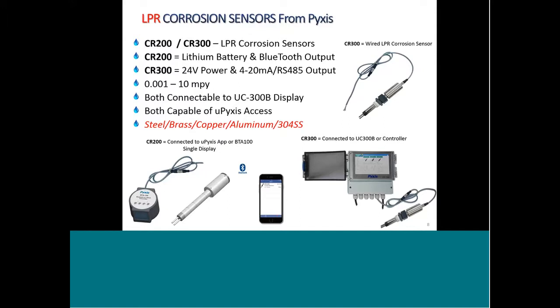It's known as two primary product lines. One is CR200, and the second is CR300. I'll start with CR300. That's the device on the upper right corner of the screen. This is an LPR corrosion sensor that is self-contained. It requires no intermediate transducers, no specialized controllers, no specialized recording devices. We built it so that it can be powered by any conventional cooling tower controller that provides simple 24-volt power and can receive either a 4 to 20 input signal or a Modbus input signal.